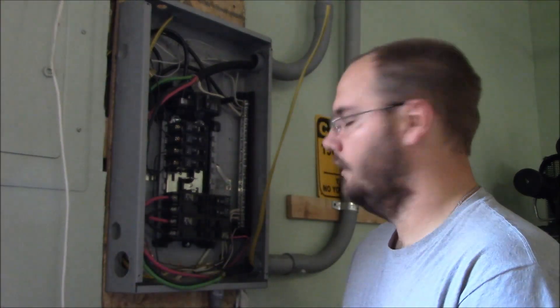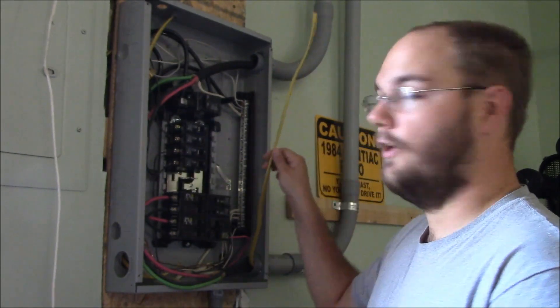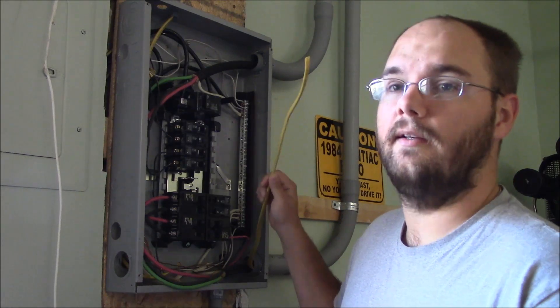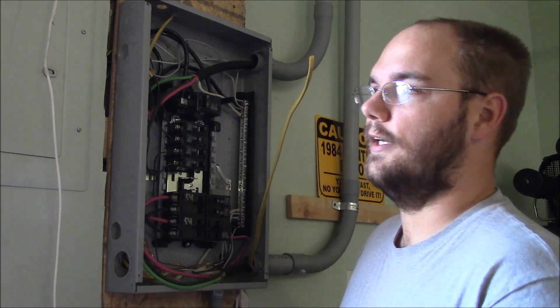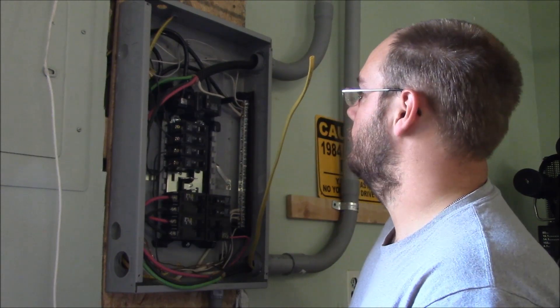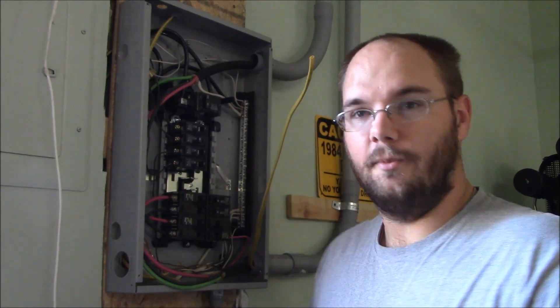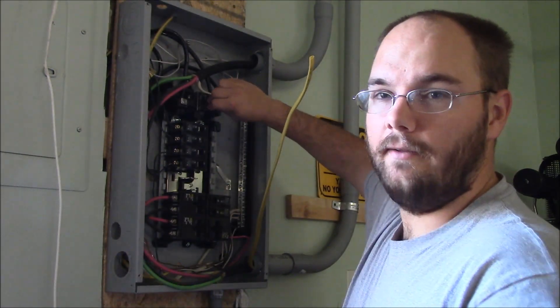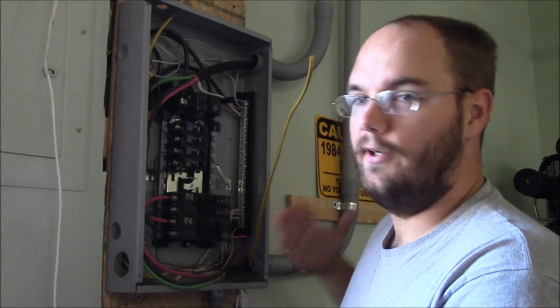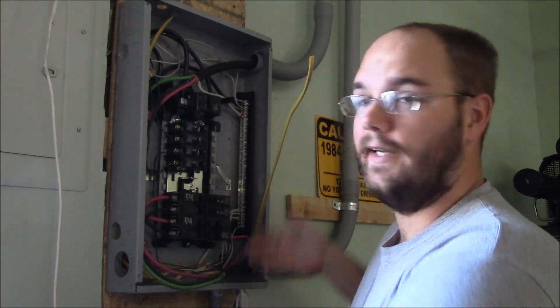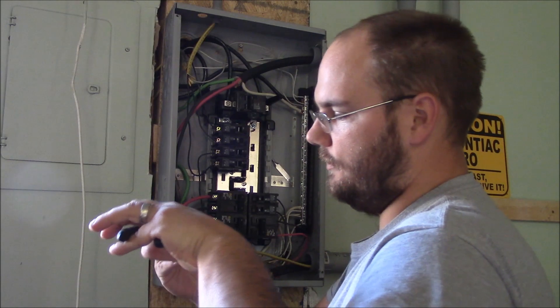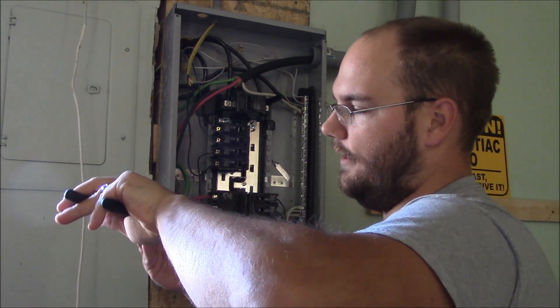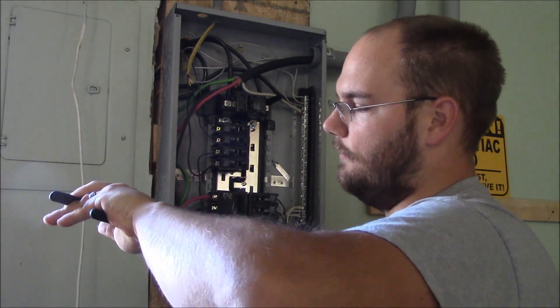This one I'm going to be putting in a new circuit for some additional lighting using a 20 amp breaker. We're going to start by—this wire is currently not connected to anything, it's dead, so we've got to connect this to the power source and the grid. The first thing that I'm going to do, I don't really think I'm going to lose a lot of light, I got a decent window here—I'm going to turn off the main so that there's no power going to any of this in here.